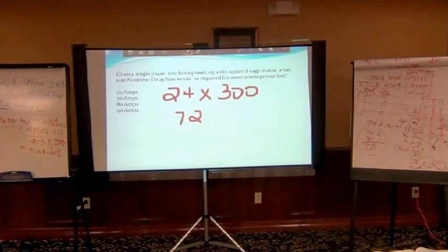The second thing is round it down or round it up. If you had 72, if you had permission, then you would round that up to 75. Right, there's no 75, so you'd round it up to 80. So I could get those top three either by using just the exception or exception number one. If you had an exception there, you would round up to 80, right? Correct. If they give you permission to use any allowable exceptions or permissions, then it would round up.